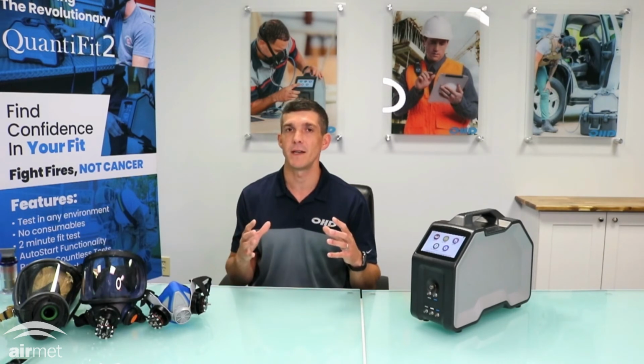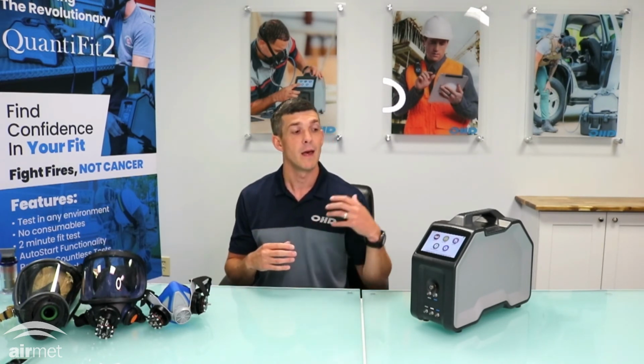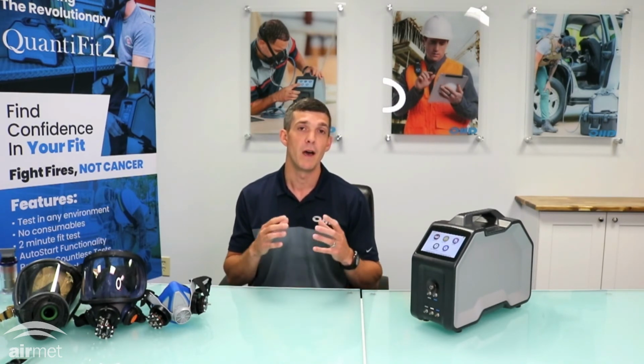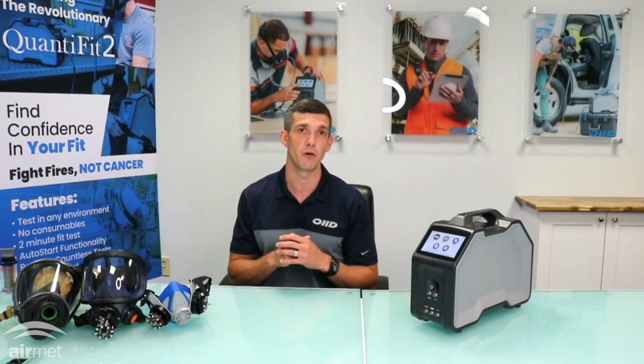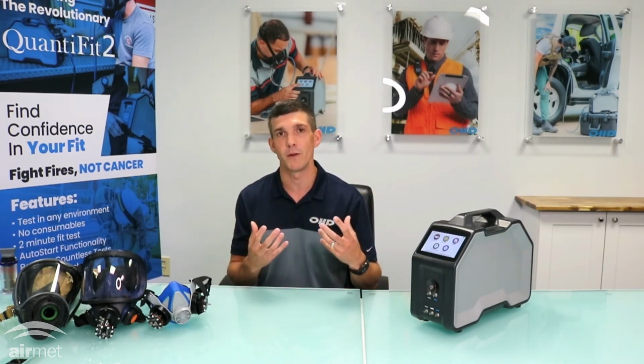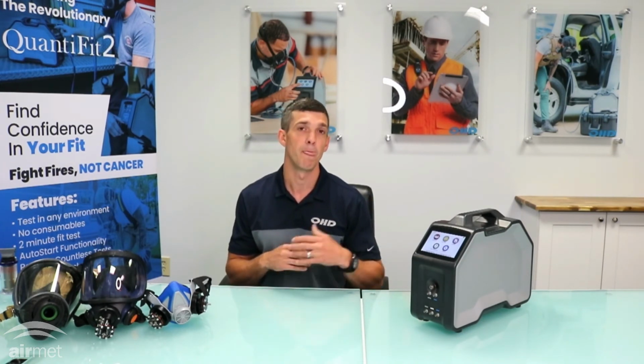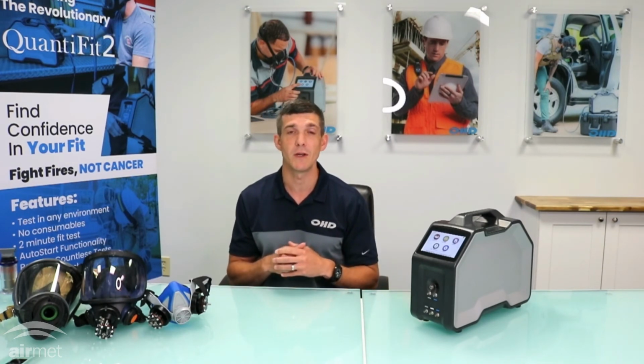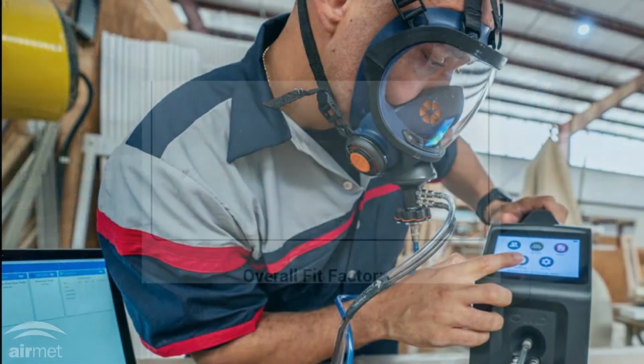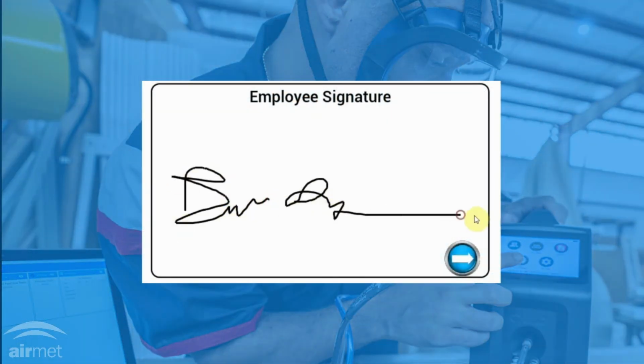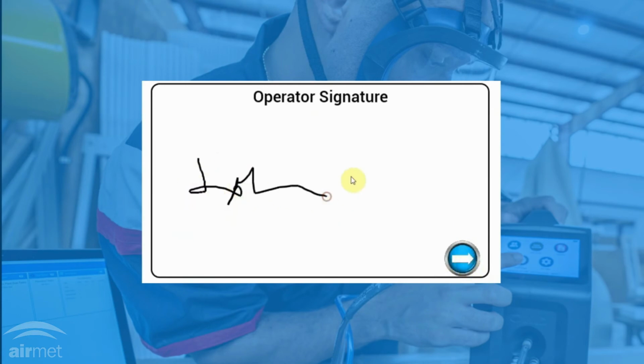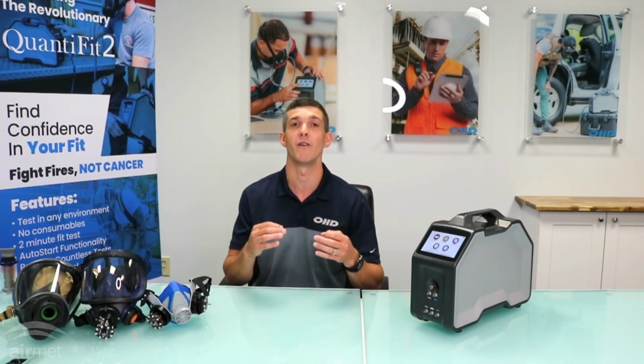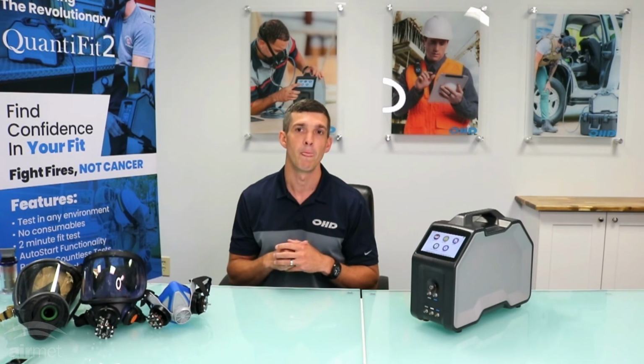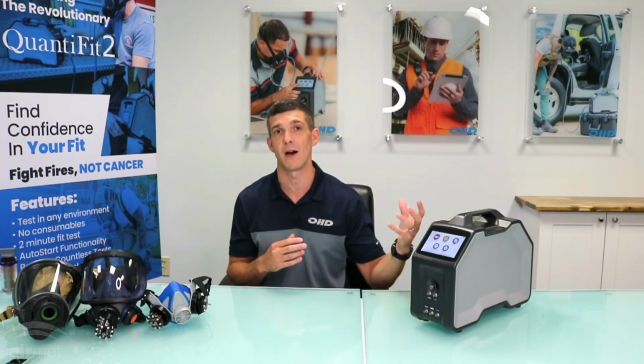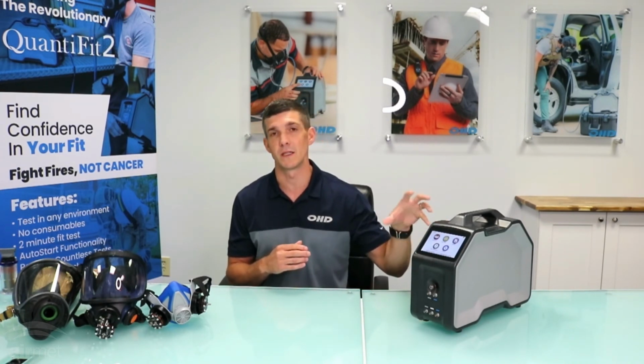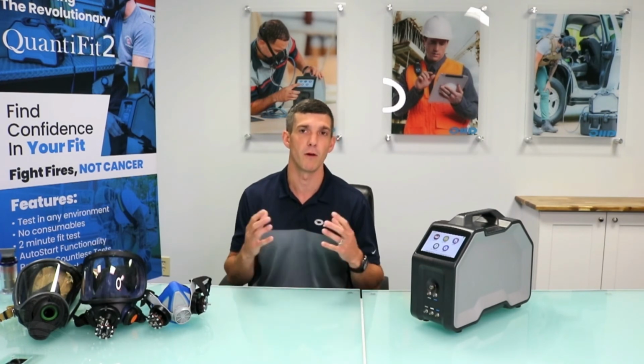Interactive troubleshooting. Within fit testing, there are times where you have failed steps or issues with testing, and the unit now has, through the software and onboard storage, interactive troubleshooting feedback based on the failure graph. So as you're testing people and you interact with those failures, you get that interactive troubleshooting with the technology. Color touchscreen display. On-screen signature capture is a major feature that we've added for test validation. After a test is finished, you have a signature capture by the person being tested and also by the operator before they start conducting tests. Those go onto reports, so you have saved PDF files without having to print out paper and sign those all through the new technology. Expanded onboard data capability. Virtually thousands and thousands of records can be saved on the unit itself without using a computer, and obviously with the OHD Logic software, virtually unlimited.